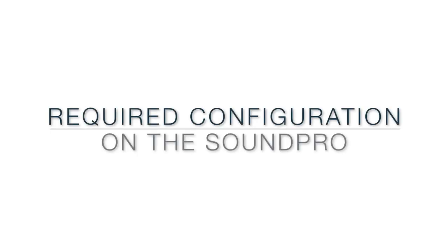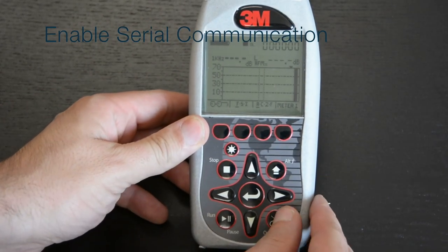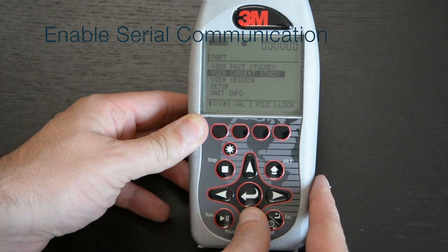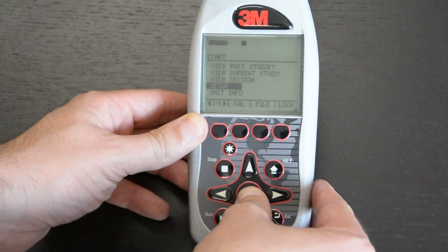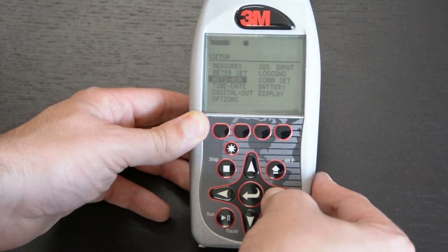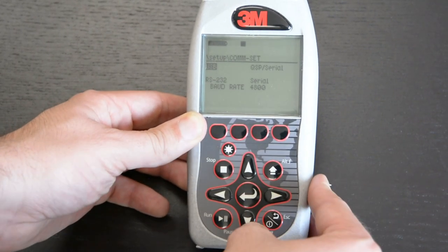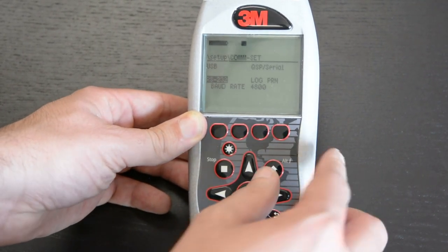In order to begin transmitting data from the SoundPro to the FX-30, we'll first ensure that the proper logging options are set. We'll do that by pressing the Escape button, then selecting Setup from the menu screen, then navigating to Comm Set, selecting that, then changing the RS-232 field from Serial to Log PRN, and then ensuring that the baud rate is set to 4800.